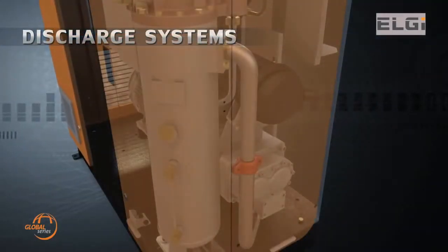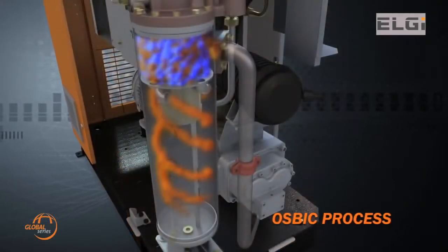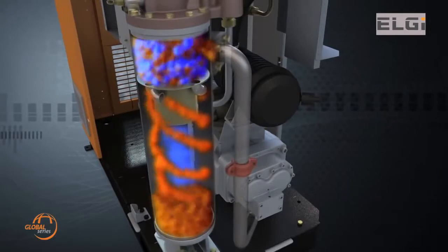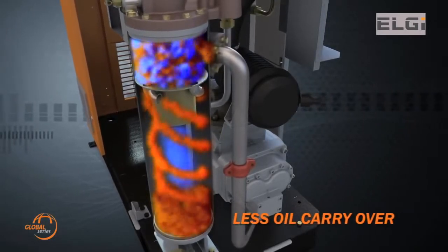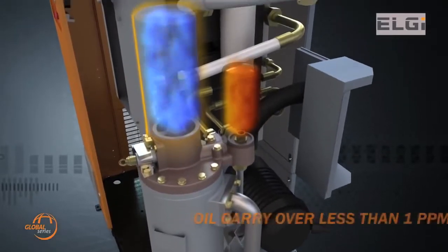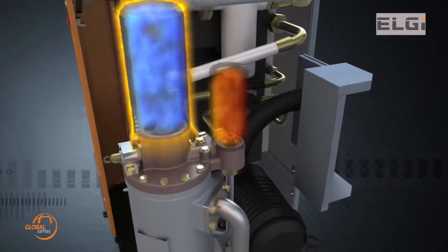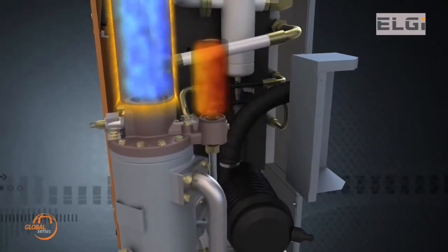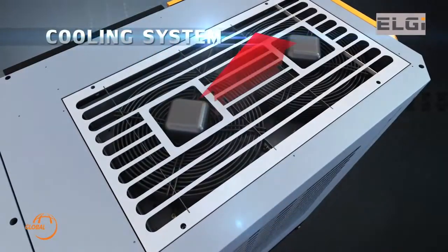ELGi has applied the unique OSBIC process — oil separation by impact and centrifugal action — which enables efficient air and oil separation with minimum pressure drop. This method enables pre-separation of the oil mixture to a greater extent and delivers consistent oil-free air by passing it through a separator element.